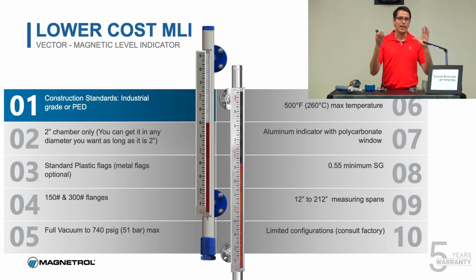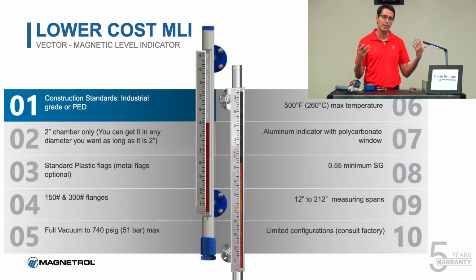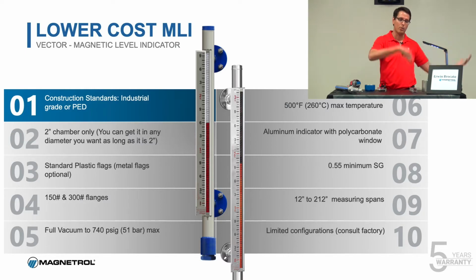So the limitations, or I guess the simplifications to the device versus our other models. Obviously less configuration. So no B31.1 construction, no B31.3 construction. Those are the construction and piping codes required for process in a refinery, which is B31.3, and power piping, they call it, which is B31.1. B31.1, all that means is if you connect it to an auxiliary tank that's connected to a boiler, you have to meet certain requirements when you're building and when you're welding chambers or pressure vessels. And we don't have that for this particular device. So you can't put it on a boiler system, and you cannot put it in a refinery. So that's one of the limitations.